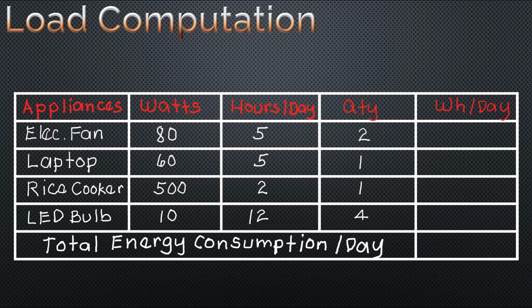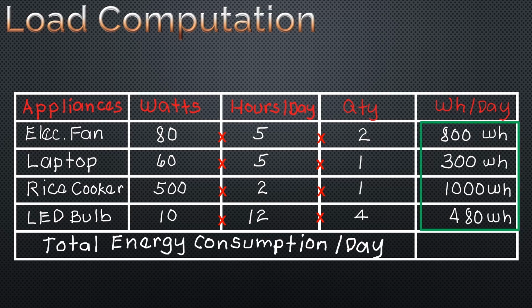So to find the watt-hours per day of each appliance, you will multiply the watts, hours per day, and quantity. So 80 times 5 times 2 is 800 watt-hour. 60 times 5 times 1 is 300 watt-hour. 500 times 2 times 1 is 1,000 watt-hour. 10 times 12 times 4 is 480 watt-hour. So to get the total energy consumption per day, just add the watt-hour per day of all appliances. And the total for our example is 2,580 watt-hour. And that is our load reference per day.